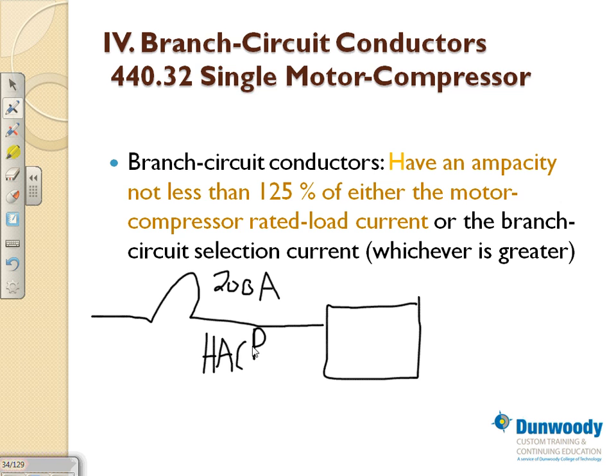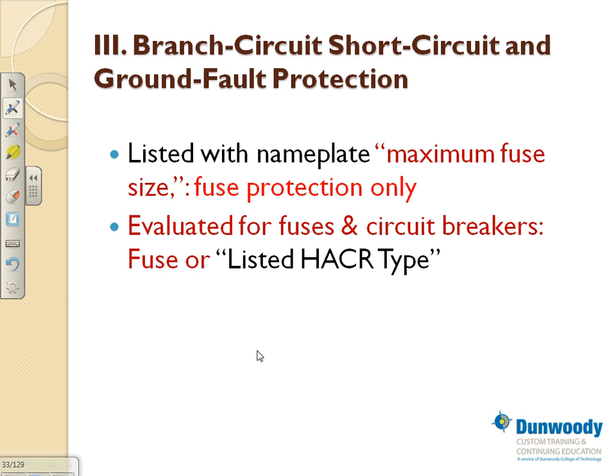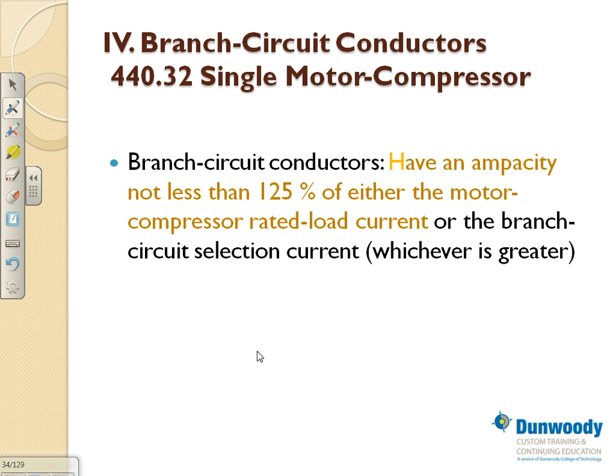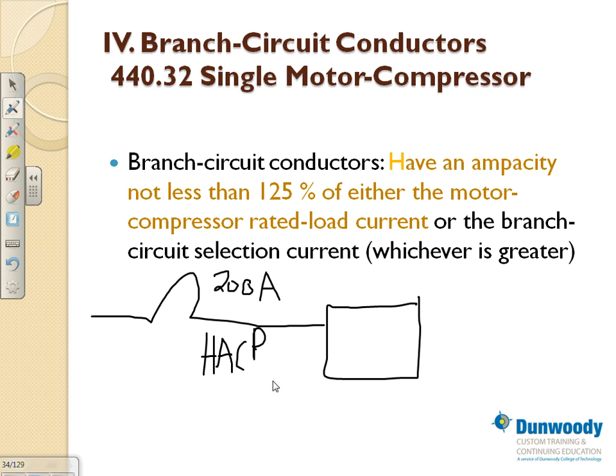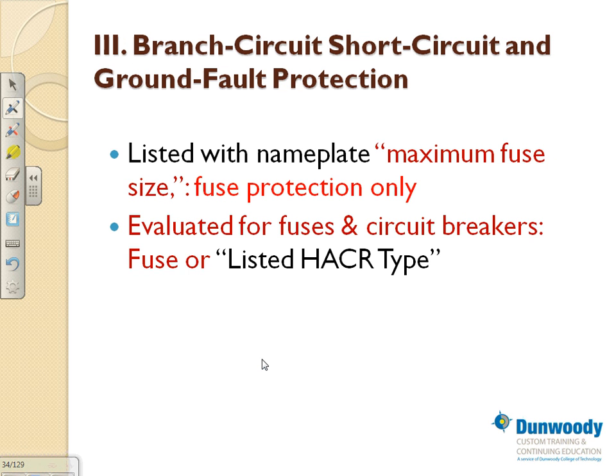HACR, is that how they spell it, the term that they use? Yep. HACR. If it says a fuse, then you have to put a fuse. Now what happens if they say a fuse and you have a circuit breaker panel? What would you do? You can't put a fuse in a circuit breaker panel, right? So you put a circuit breaker in the panel, and you bring the feeder right next to the HVAC equipment, and you put a fuse disconnect right next to it. Solve the problem. You give them their fuse right next to the equipment.